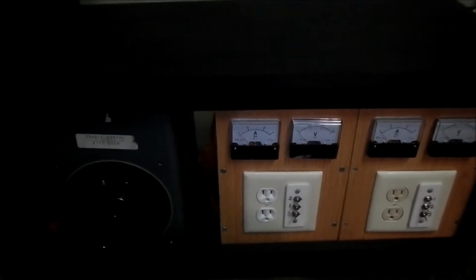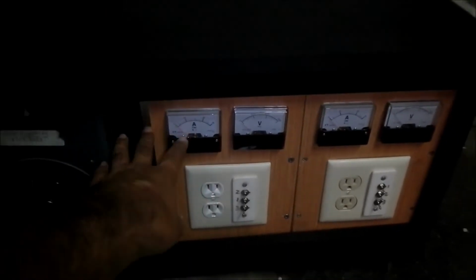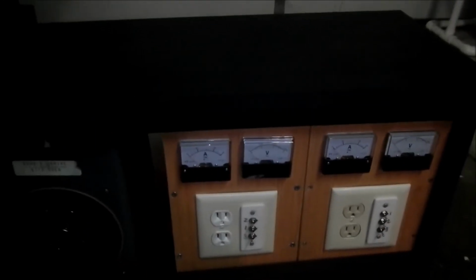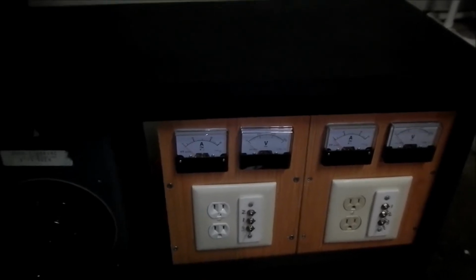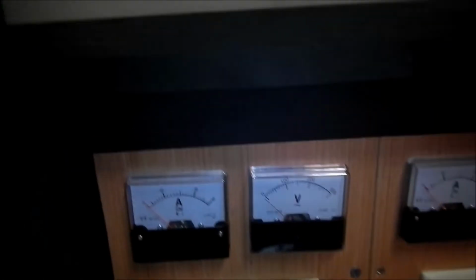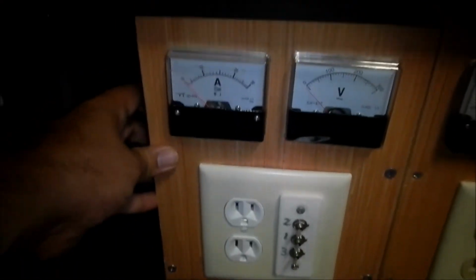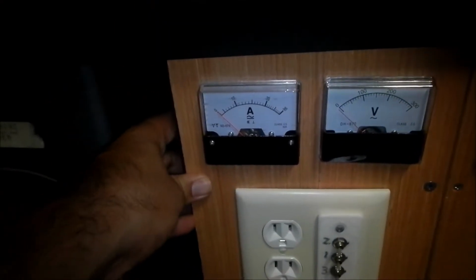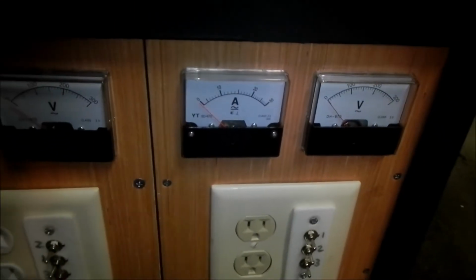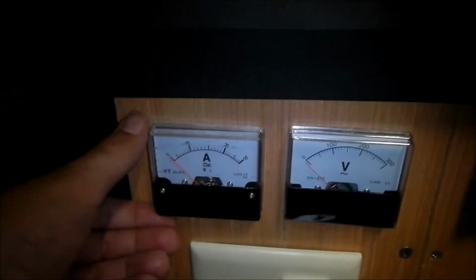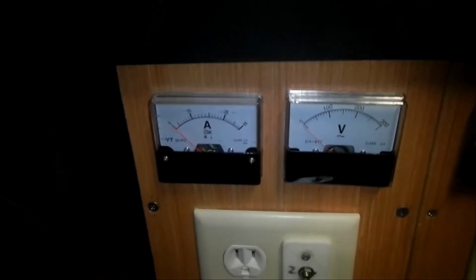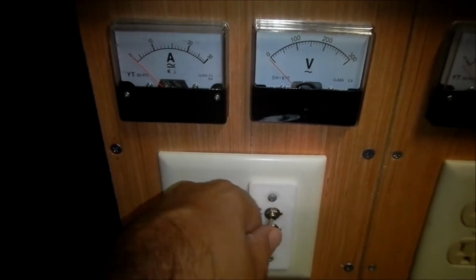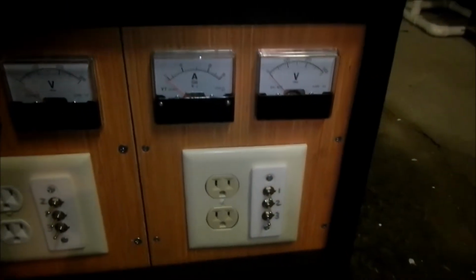I can run this at 240 with each one of my power control units on a 120 line, so I have these two units stacked in here. This one is for one phase of the 120, and this one is for the second phase of the 120. I've got my amp and voltmeter for each line, and I have the switches that control the power factor correction caps.